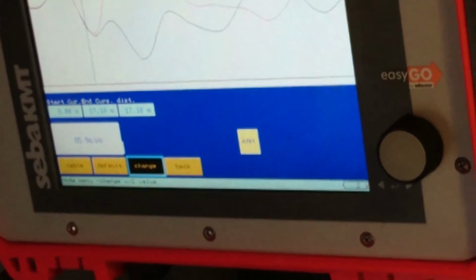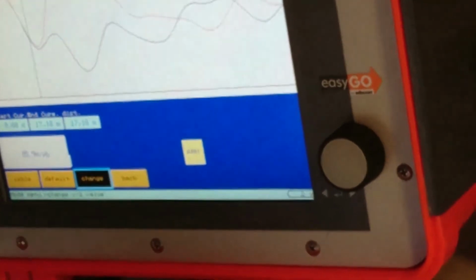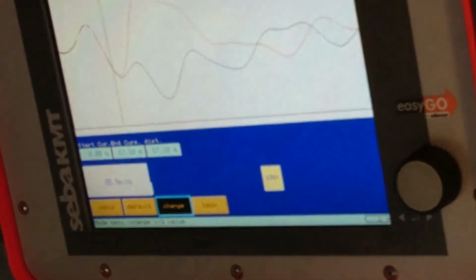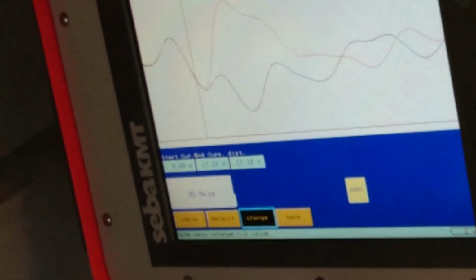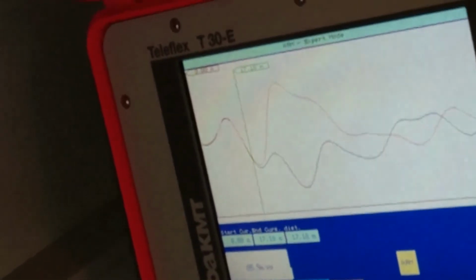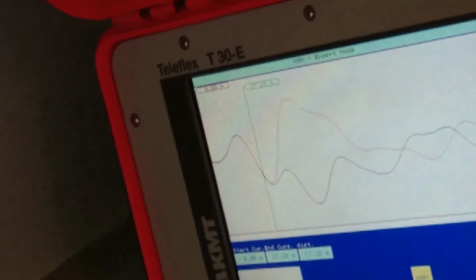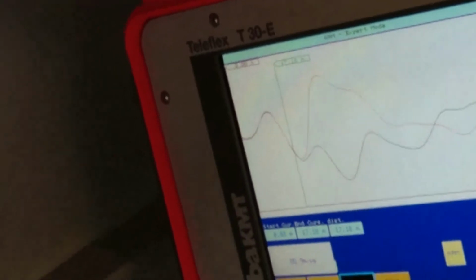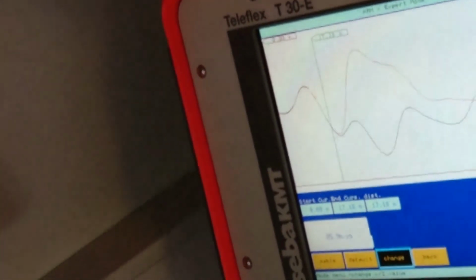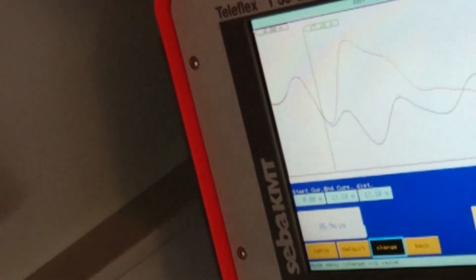So I will suggest this: you take a sample cable around 20 meters or 25 meters length, you do this test on it, and then you fix and make the correct length of the cable, not by guessing. That's not okay, because I don't know if my steps were good or not. It's just around, so you make the exact length and then calculate the velocity factor, and use it anytime you do this test.